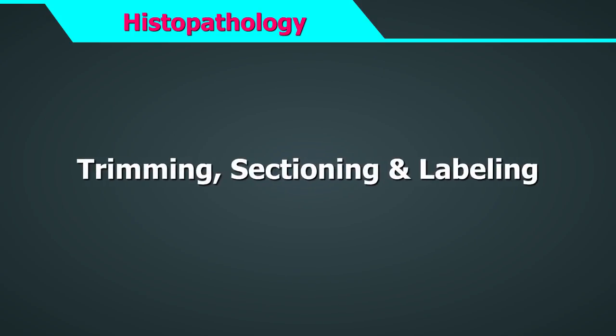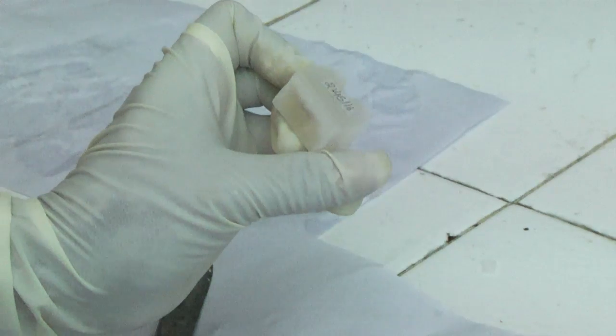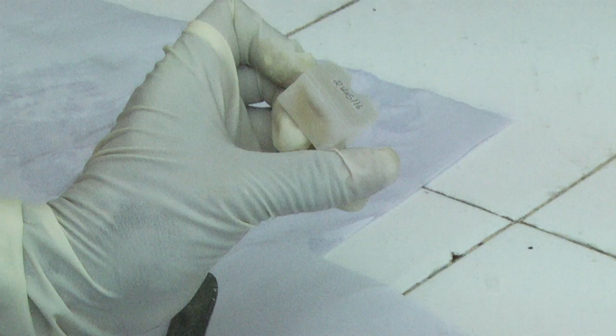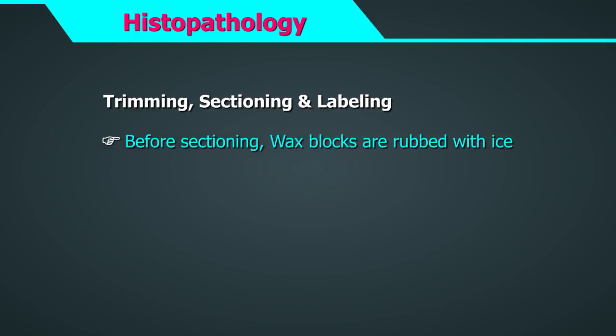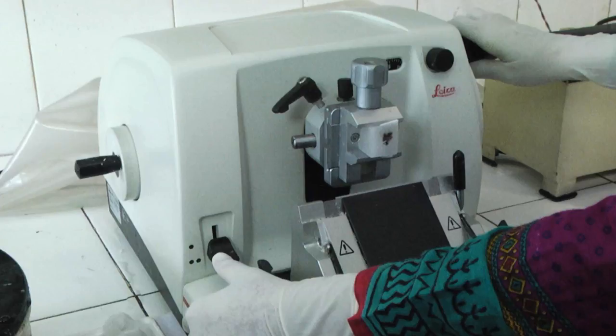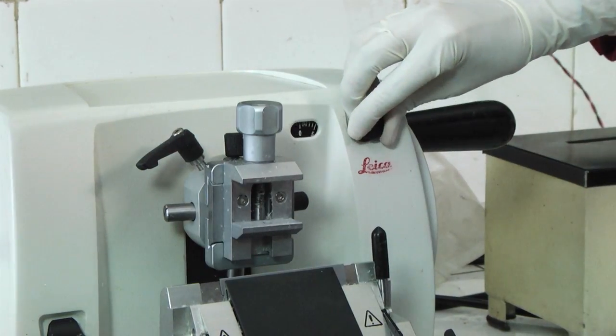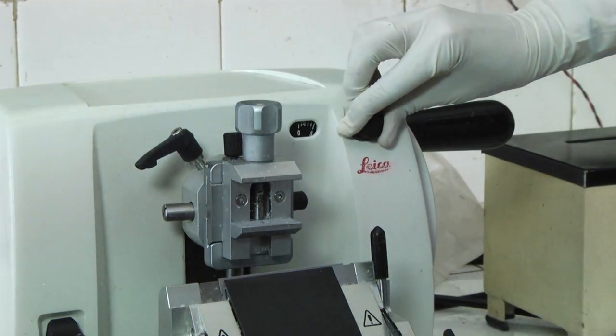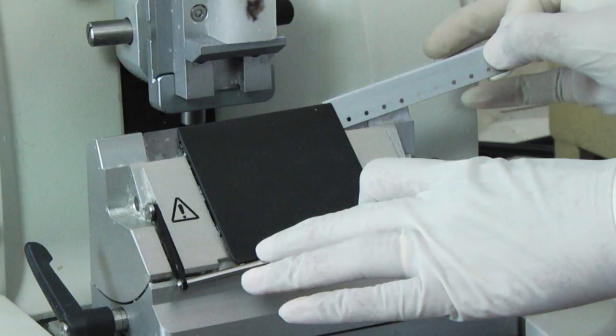Trimming is done to remove excess wax from the blocks until tissue is fully exposed. Boundaries are cut manually to decrease the size of the section. Before starting sectioning, the wax blocks with embedded tissue are rubbed with ice. The microtome is used to cut tissue sections 4–5 micrometres thick, one tissue block at a time. The microtome is essentially a knife with a mechanism for advancing a paraffin block standard distances across it. The setting of the microtome indicating tissue thickness should be checked before use. The important necessity for proper sectioning is to have a very sharp knife.